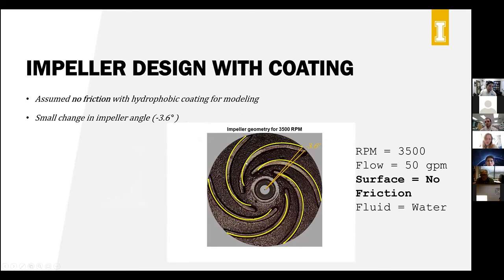And this is what we saw as the impeller angle change from the actual to the modified. And we're taking this negative and positive angle as negative being the angle of attack at the outer periphery rotated counterclockwise, and positive is clockwise. So this is the same design for 3,500 RPM, same flow, no surface friction and the water.